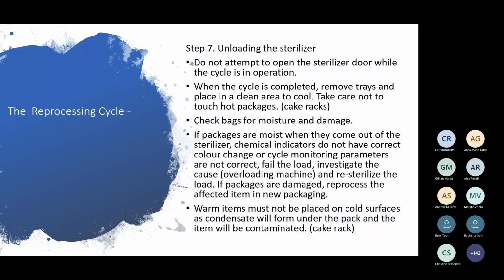You want to make sure that you check your bags for any moisture and damage. Excuse me. If packs are moist when they come out of the sterilizer, the chemical indicators do not have the correct color change, or cycle monitoring of the parameters are not correct, fail the load and investigate the cause. Could be that you've overloaded the machine. You might have put too much on. You might know how many kilos of instruments you're supposed to be able to load in your machine, and re-sterilize the load. If packages are damaged, reprocess the affected items in new packaging.